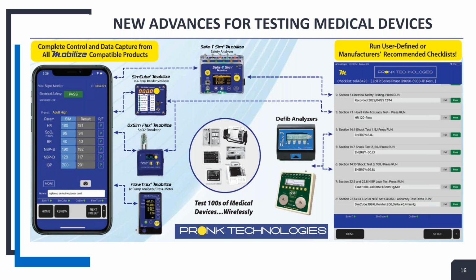And so the procedure requires the technician to follow the procedure all the way through. And you can see here, if there's a test involving a particular heart rate and such, you need to follow those tests. In this case, there's an alarm test you've got to do, and it tells you what the test is. You can kind of see down below. What does it want us to do next?